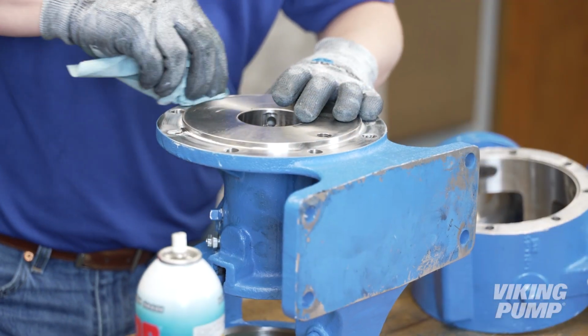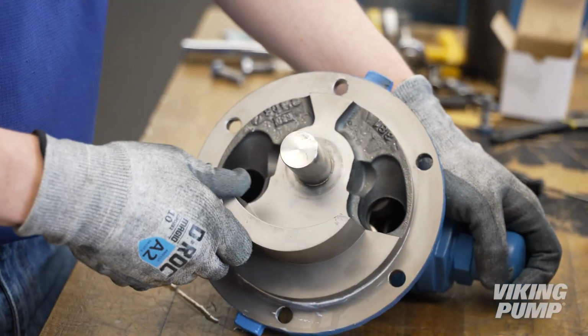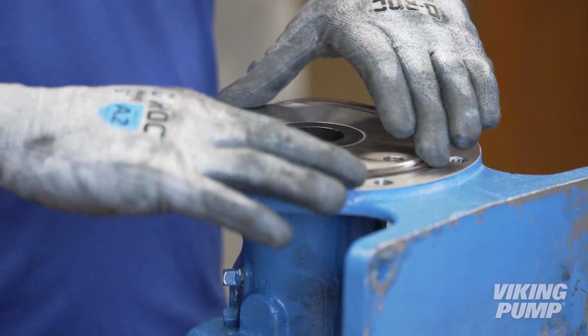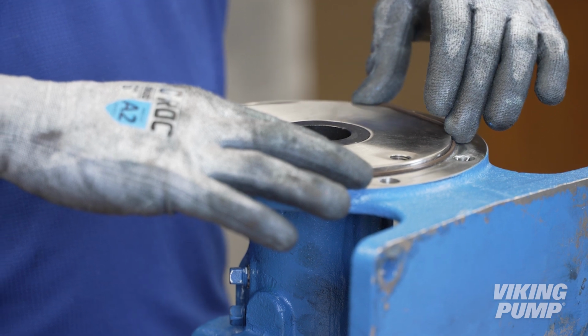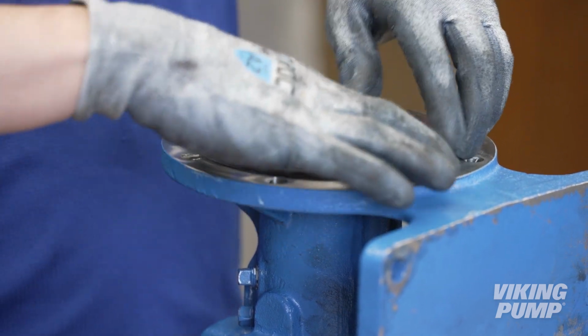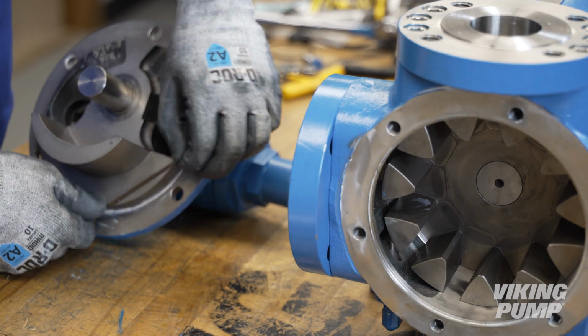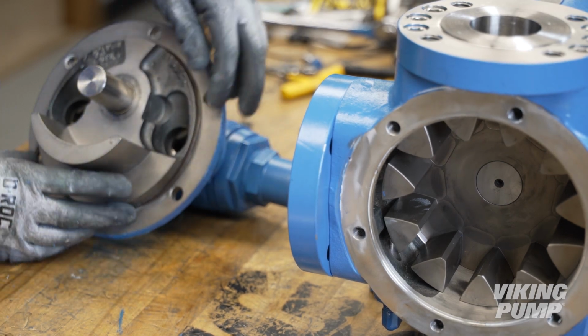When reassembling, ensure the sealing surfaces are clean and free of debris. As you reassemble the pump, install an O-ring or gasket into the grooves on the bracket and head. Use O-ring lubricant for O-rings and gasket sealant for gaskets.